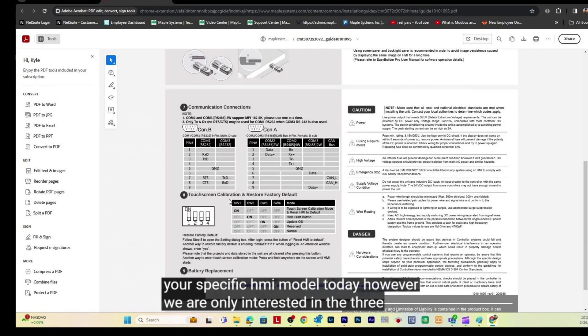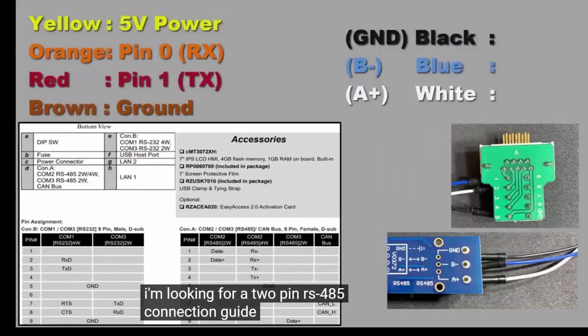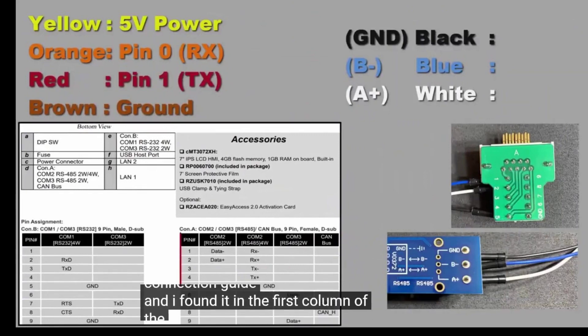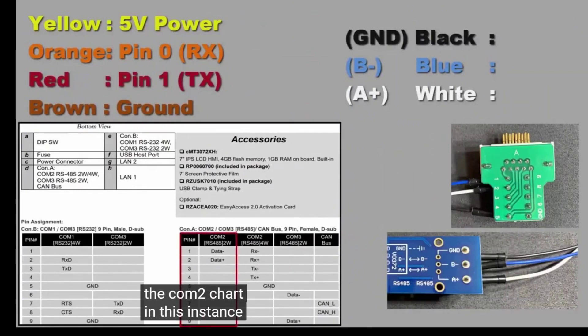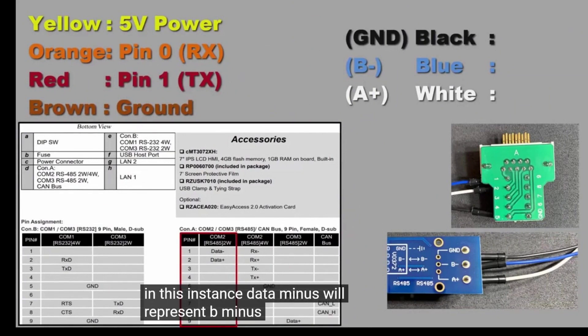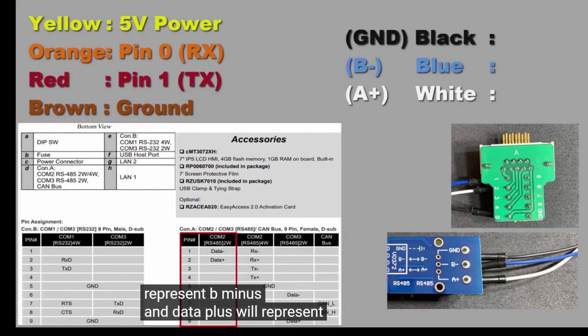However, we are only interested in the 3 charts at the bottom. I am looking for a 2-pin RS-485 connection guide, and I found it in the first column of the COM2 chart. In this instance, Data-minus will represent B-minus and Data-plus will represent A-plus. With this knowledge, I know the blue wire will connect to pin 1, and the white wire will connect to pin 2.